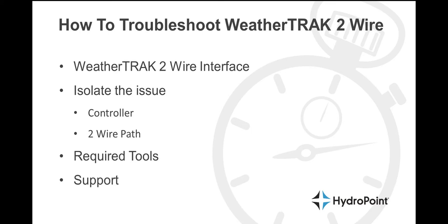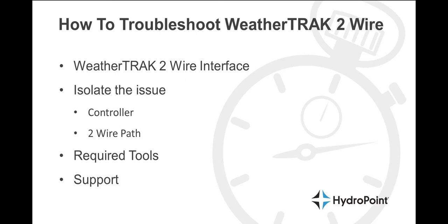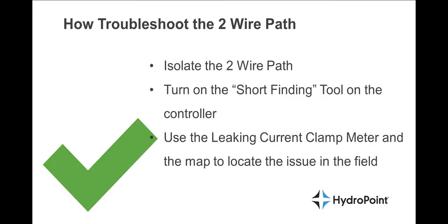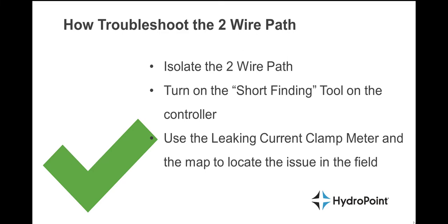The next question is always: where on the 2-Wire path? Let's talk about the WeatherTrack features that help find the problem. The first step in troubleshooting the 2-Wire path is isolating that path with the switches, keeping on only the path suspected of having a fault. Leave the bad path on and turn on the short finding tool on the controller.